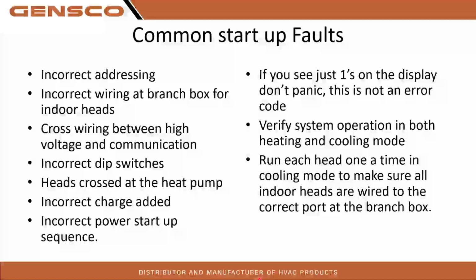So what you'll do is put those units one at a time in cooling and make sure that the head that's calling is actually getting cold. And check the other heads that are off, to make sure the coil's not starting to freeze up or get extremely cold, anything like that. That's usually what ends up happening. And we get this call a lot in the summertime: "Hey, I have indoor heads freezing up on me." The number one cause for that is that it's wired wrong. You're sending refrigerant to the wrong indoor unit. So again, on all startups, you guys really should test cooling mode on each head individually, just to make sure it's wired correctly.